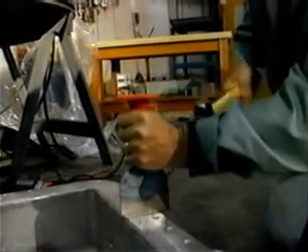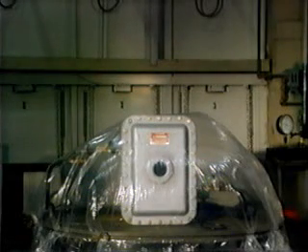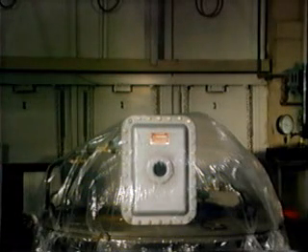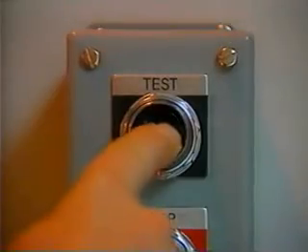Then we damage the flange. A similar result could occur if the enclosure is dropped or the bolts are not installed properly. We repeated the test again in a Group B environment. The results are dramatic.